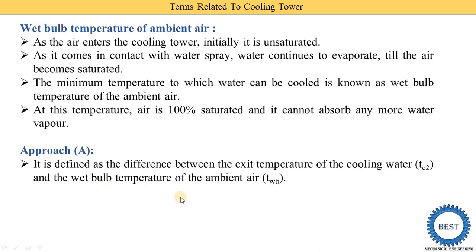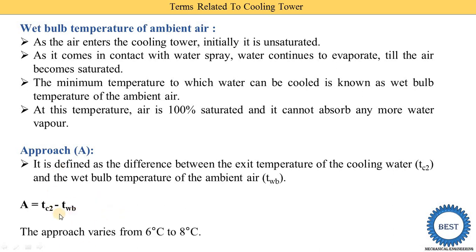The wet bulb temperature of the ambient air is denoted as TWB. The equation for approach A is: A = TC2 − TWB. Here, TC2 is the exit temperature of the cooling water — the water collected at the bottom of the cooling tower. TWB is the wet bulb temperature of the ambient air. This difference is called the approach, and its value ranges from 6 to 8 degrees centigrade.